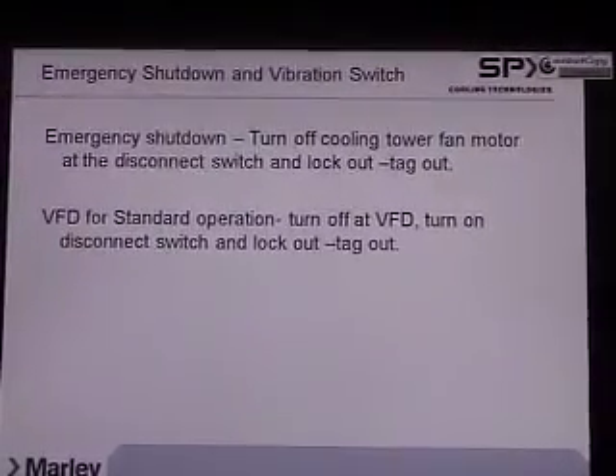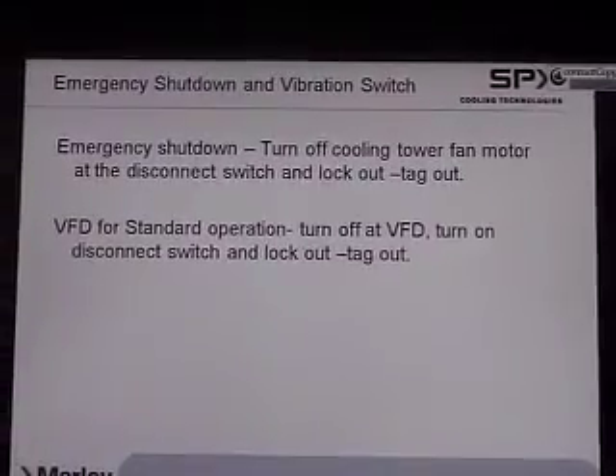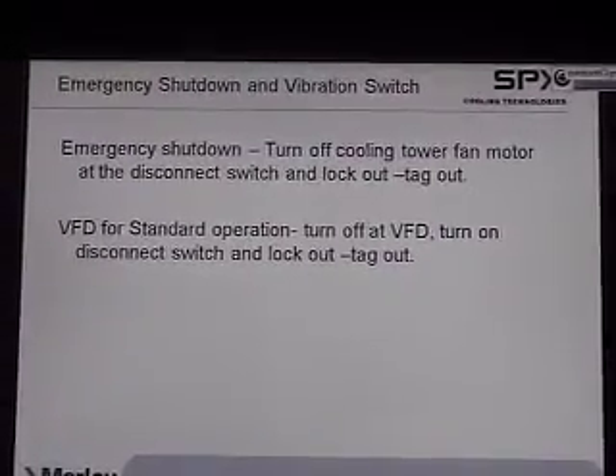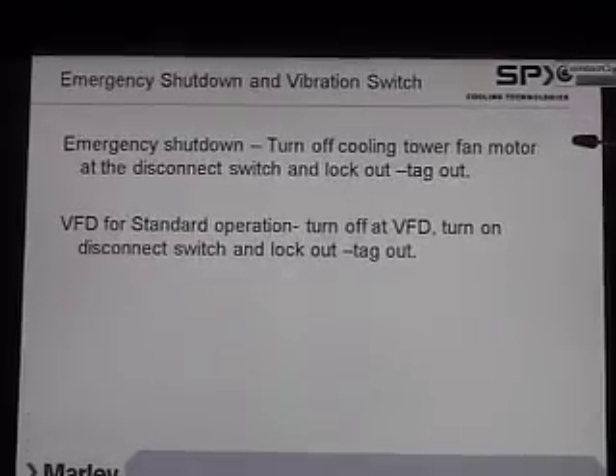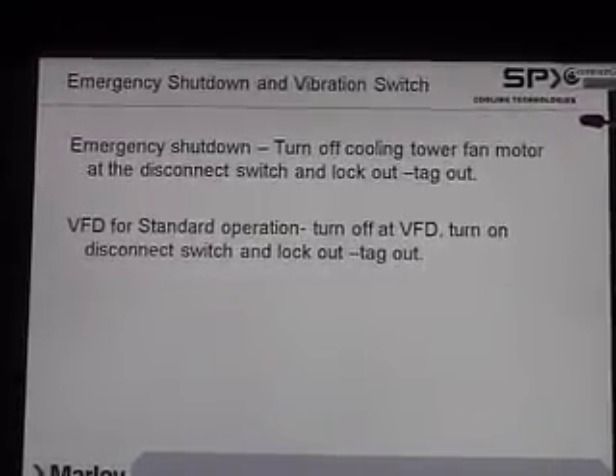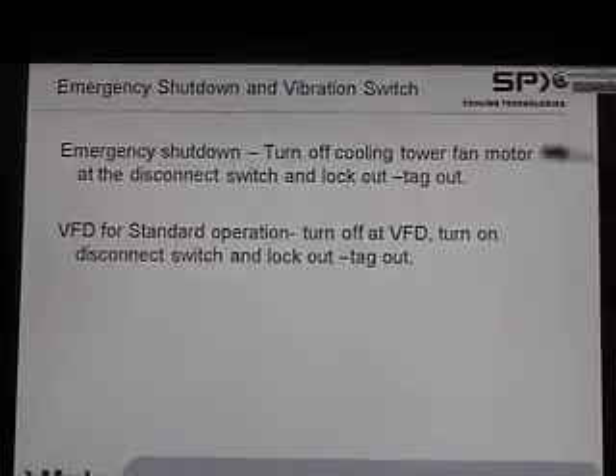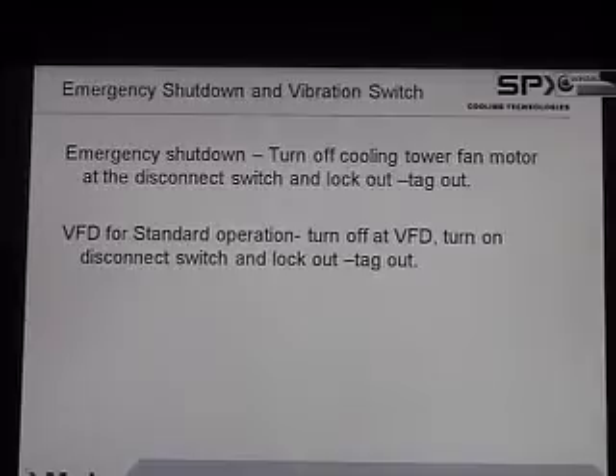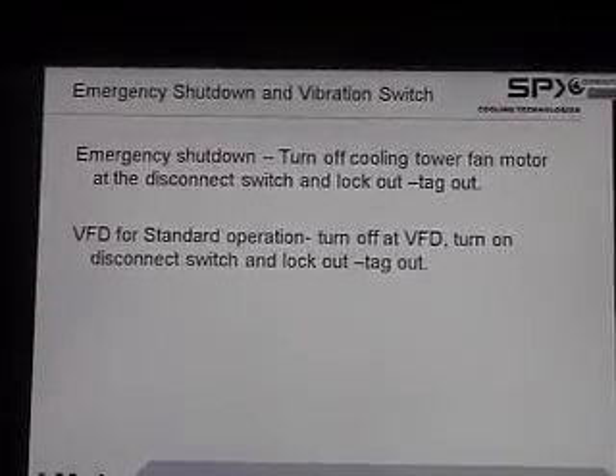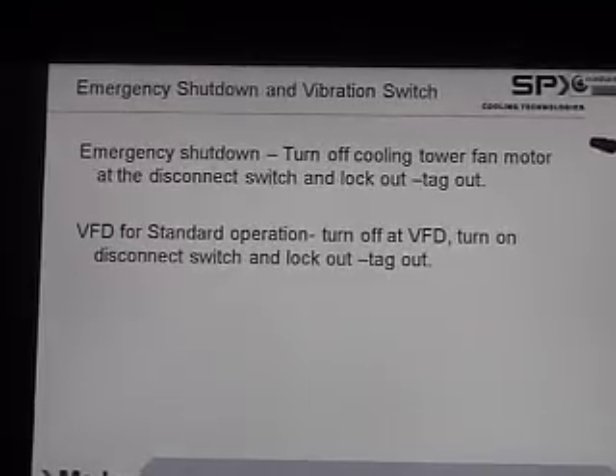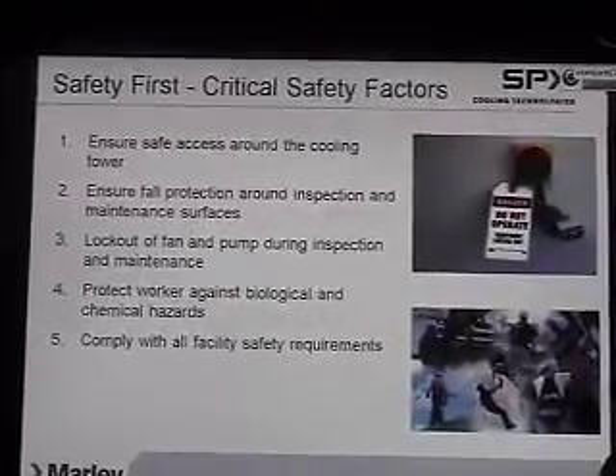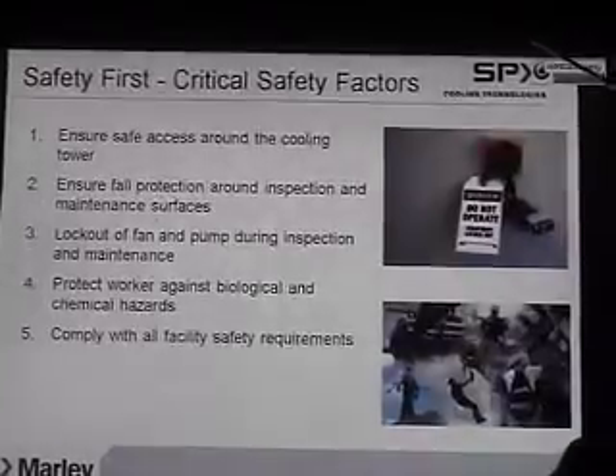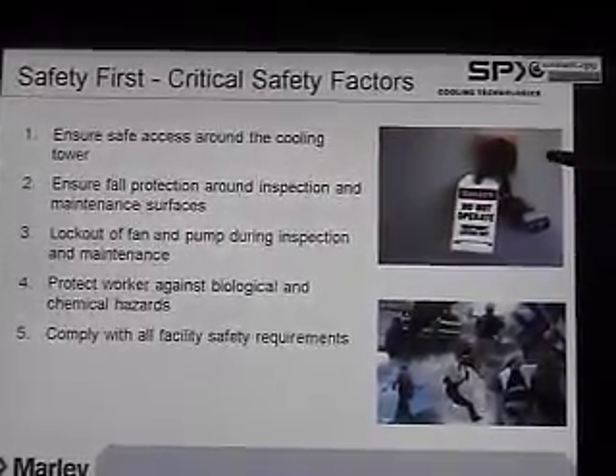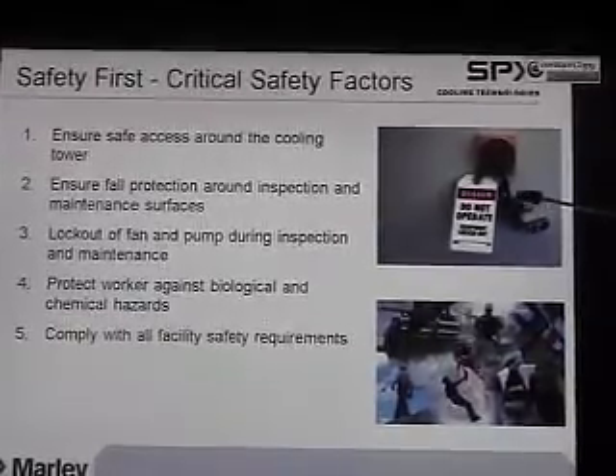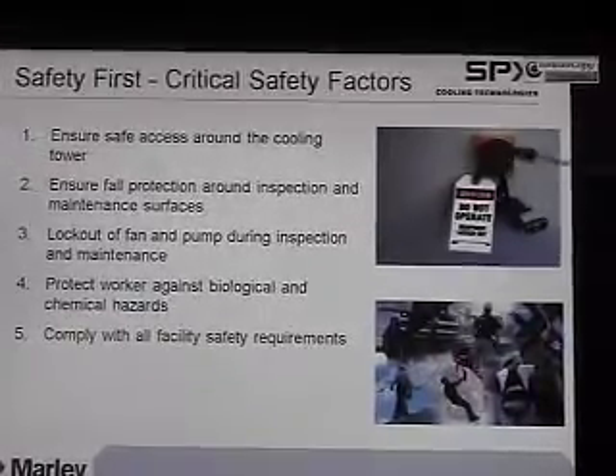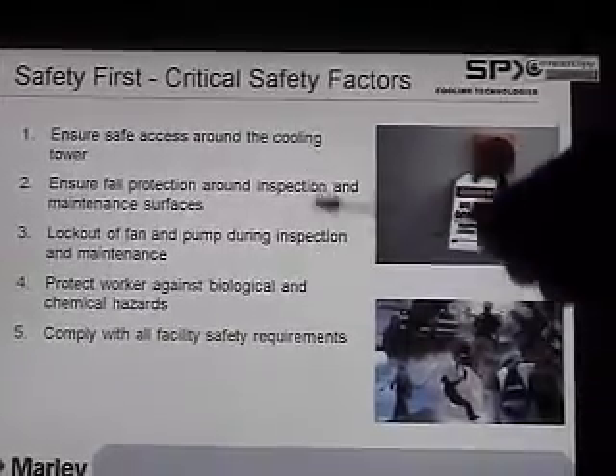Generally your cooling tower, you shut it on and off at the VFD, but in an emergency you would just turn it off at the disconnect switch that should be at each tower. And then again, VFD for standard. If it's an emergency, you would just switch it off at the cooling tower and probably lock it out, tag it out to see what's wrong. Oh, here's our lockout tagout message. Right there, see? That would be you. Lock out your motor and then inspect and see what the problem is.